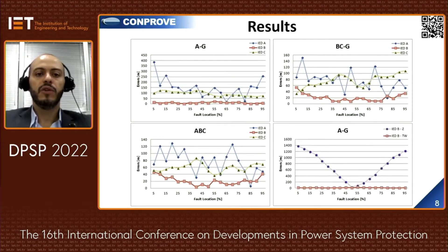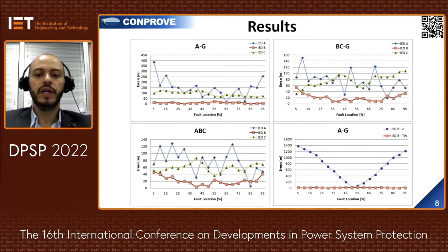It is important to note that in some cases zero-meter errors were observed. Impedance fault location errors were also catalogued for comparison. For an AG ground fault on IED B, the fault location using the impedance method — shown in purple — is compared with the fault location using traveling waves — shown in red — demonstrating the high precision of TW technology.